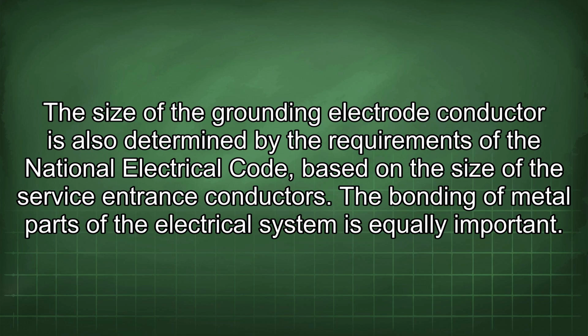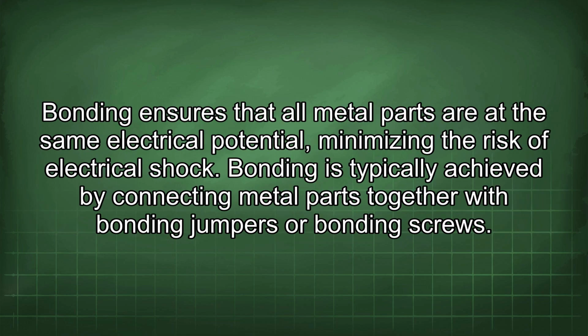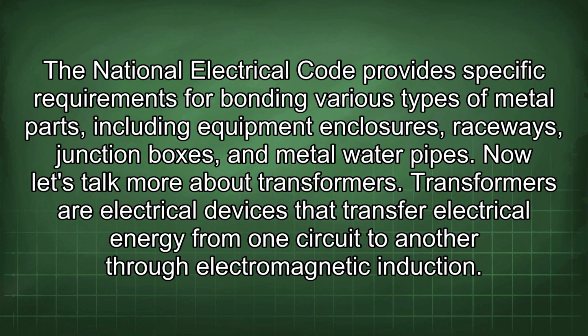The bonding of metal parts of the electrical system is equally important. Bonding ensures that all metal parts are at the same electrical potential, minimizing the risk of electrical shock. Bonding is typically achieved by connecting metal parts together with bonding jumpers or bonding screws. The National Electrical Code provides specific requirements for bonding various types of metal parts, including equipment enclosures, raceways, junction boxes, and metal water pipes. Now let's talk more about transformers.